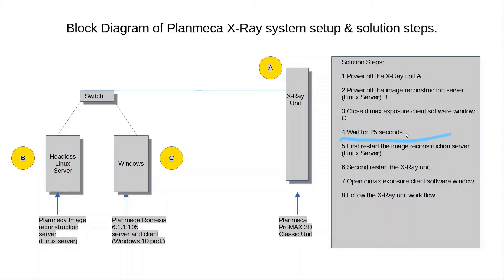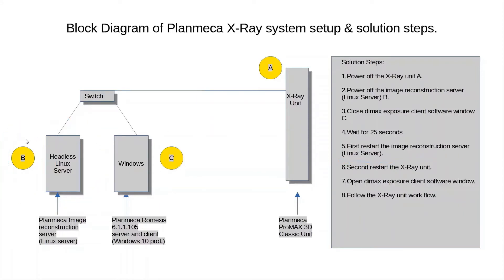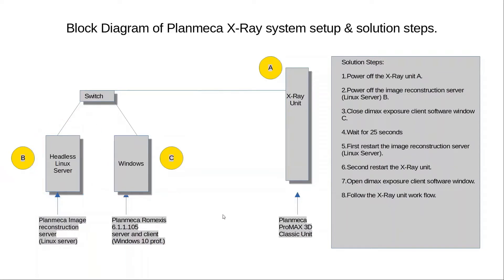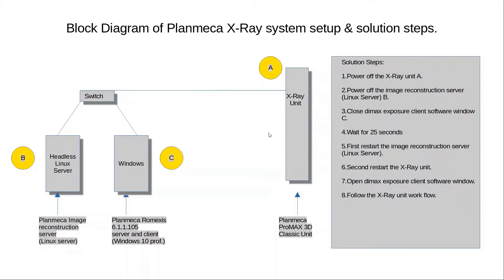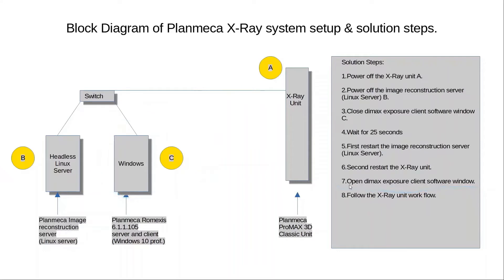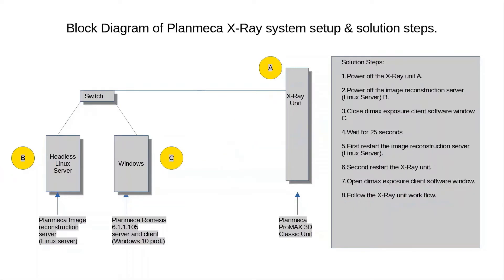Once done, move to step 5: restart the image reconstruction server. Then step 6: restart the X-ray unit. After that, come back to the Windows machine represented by C and open the dimax exposure client software window. Finally, go to the X-ray machine, follow your X-ray unit workflow, and that should resolve your issue.